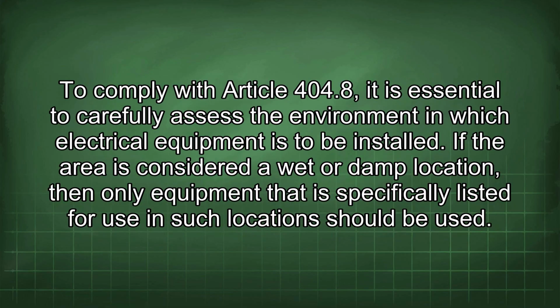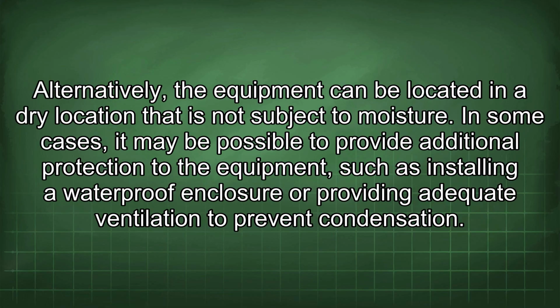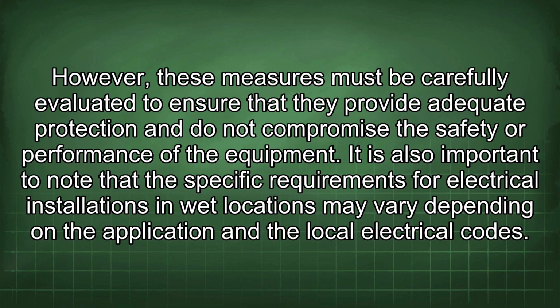To comply with Article 404.8, it is essential to carefully assess the environment in which electrical equipment is to be installed. If the area is considered a wet or damp location, then only equipment that is specifically listed for use in such locations should be used. Alternatively, the equipment can be located in a dry location that is not subject to moisture. In some cases, it may be possible to provide additional protection to the equipment, such as installing a waterproof enclosure or providing adequate ventilation to prevent condensation. However, these measures must be carefully evaluated to ensure that they provide adequate protection and do not compromise the safety or performance of the equipment.